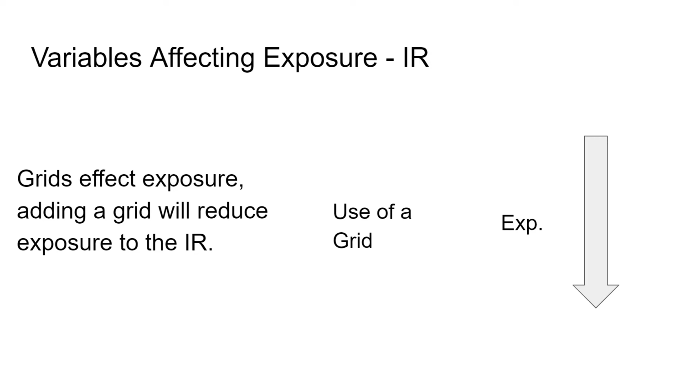Not just to make up for the scatter, but to make up for actual mostly parallel photons that get killed. And that's why as we go to higher and higher grid ratios, we have to keep increasing our exposure technique, because the little gap between the lead lines keeps getting smaller and smaller, killing more photons, even if they're not diverging that much.